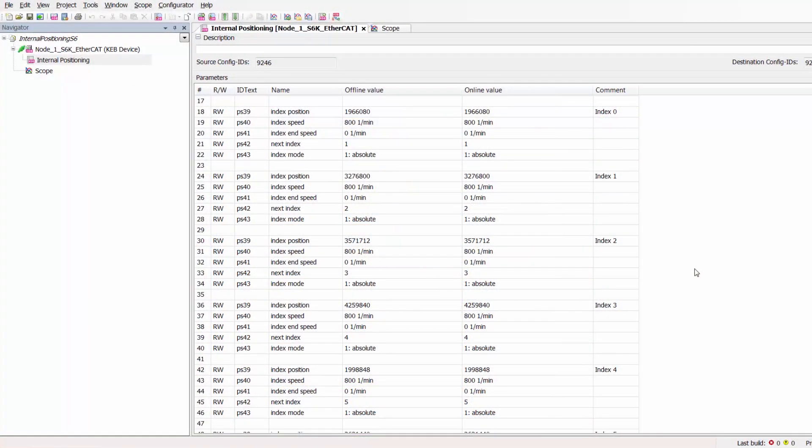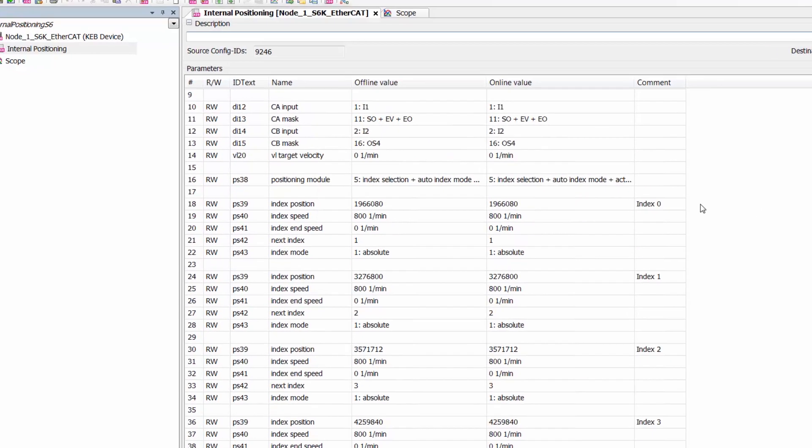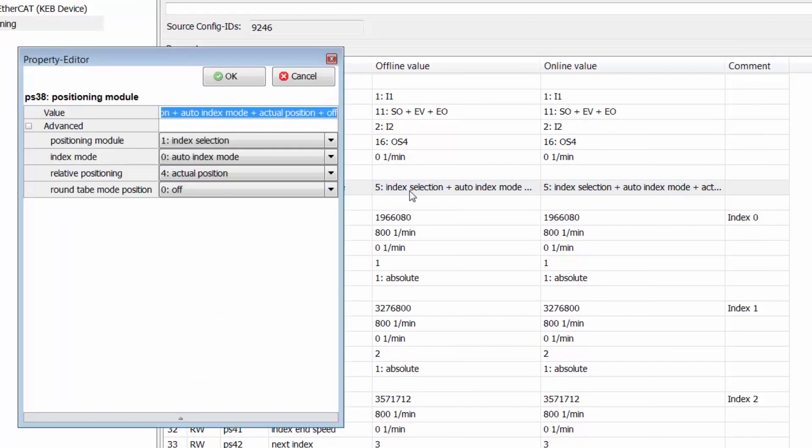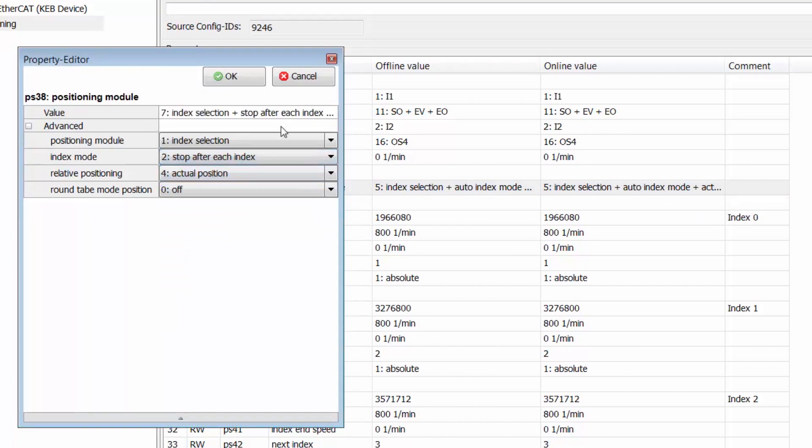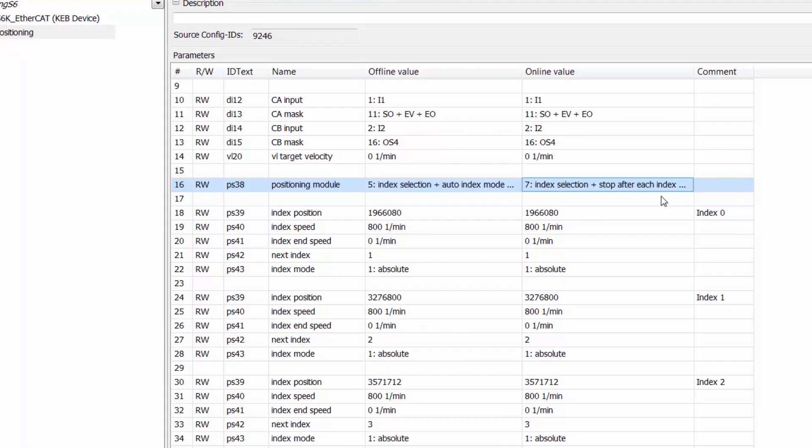We can also demonstrate the stop after each index positioning mode within the internal positioning module of the S6. To do this we will scroll up and modify our positioning module parameter inside the drive. We are going to change our index mode to stop after each index and then click OK. And we can see that this parameter was accepted in the drive.